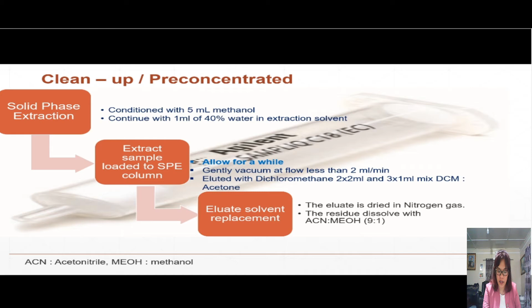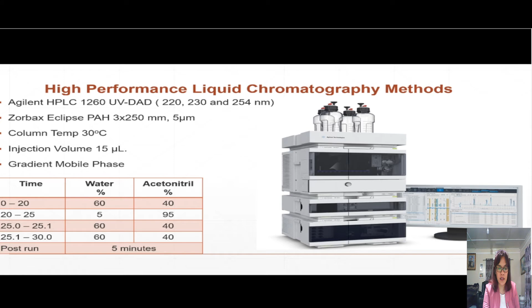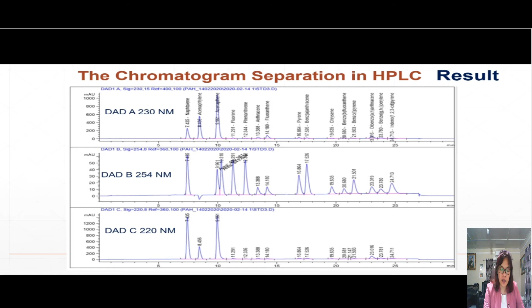The sample was measured in an Agilent HPLC with UV diode array detector at 220, 230, and 254 nanometers, in a Zorbax Eclipse PAH column with temperature 30 and injection volume 15 microliters. The mobile phase is water and acetonitrile 60 to 40 until 30 minutes. In the separation result on the column, the first peak appears at 7 minutes for naphthalene, until the last compound at 24.7 minutes for indenopyrene. The absorbance shows that at 220 naphthalene has high intensity, while acenaphthylene has high absorbance at 230 nanometers. The other 14 compounds have nice separation and are selected and detected at 254 nanometers.